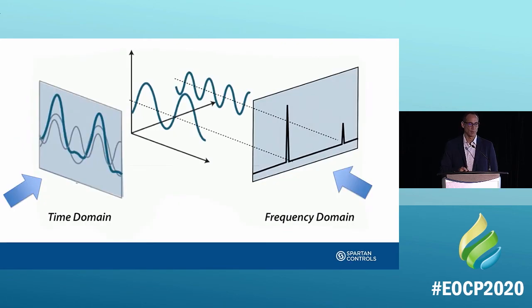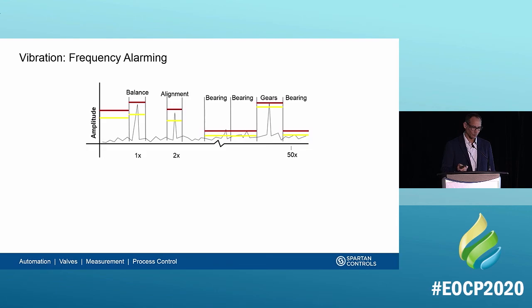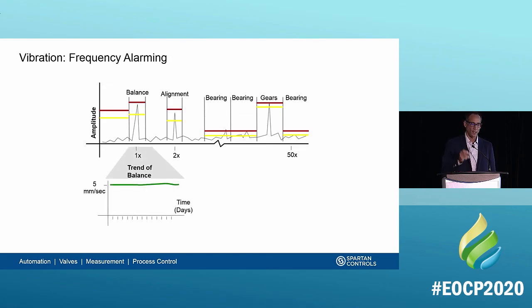To break out the individual frequency components, we do a Fast Fourier Transform (FFT) on the time-based waveform. This mathematical algorithm converts the time-based waveform into a frequency spectrum — a series of frequency signals each with a separate amplitude. We can then isolate the amplitude of the frequency associated with each mechanical part in the device. For example, balance issues occur at one times turning speed; alignment issues may appear at two times turning speed; bearings and gears occur at different characteristic frequencies. We can then trend each of those frequencies over time and see if they exceed an alarm point — for instance, at 50 times turning speed for certain bearings, an amplitude above the alarm threshold indicates a bearing problem.